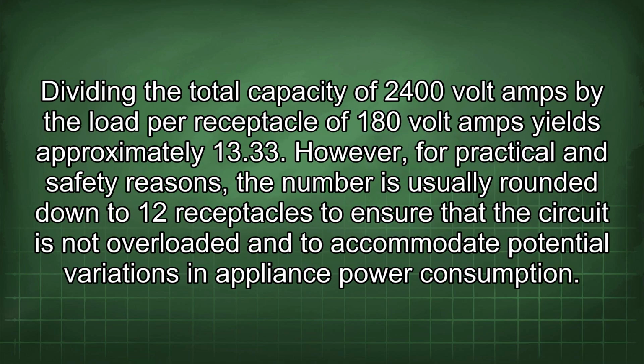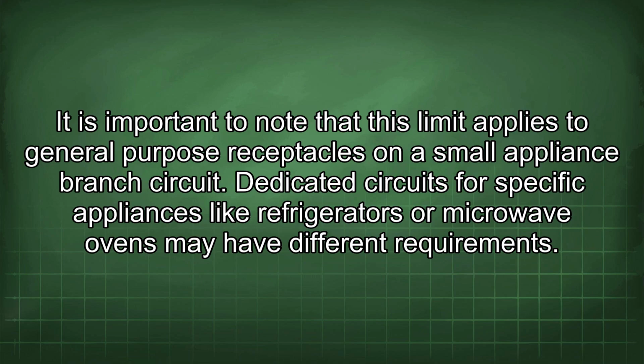Dividing the total capacity of 2400 volt amps by the load per receptacle of 180 volt amps yields approximately 13.33. However, for practical and safety reasons, the number is usually rounded down to 12 receptacles to ensure that the circuit is not overloaded and to accommodate potential variations in appliance power consumption. It is important to note that this limit applies to general-purpose receptacles on a small appliance branch circuit. Dedicated circuits for specific appliances like refrigerators or microwave ovens may have different requirements.